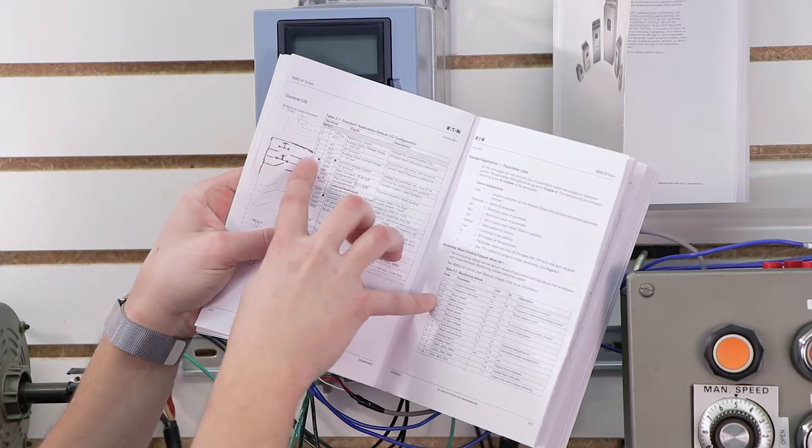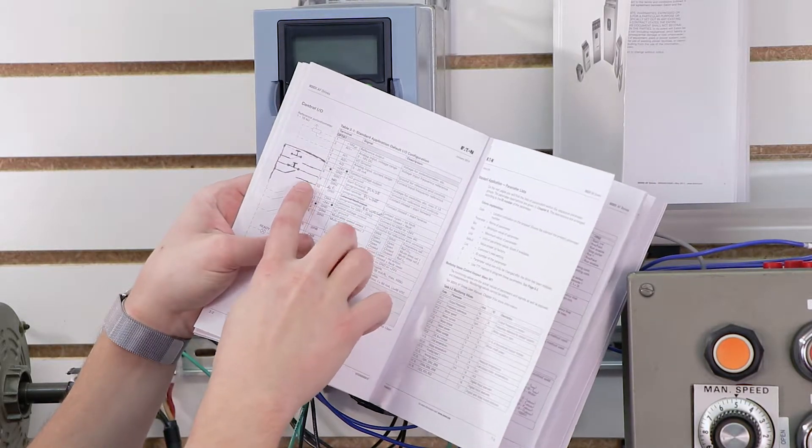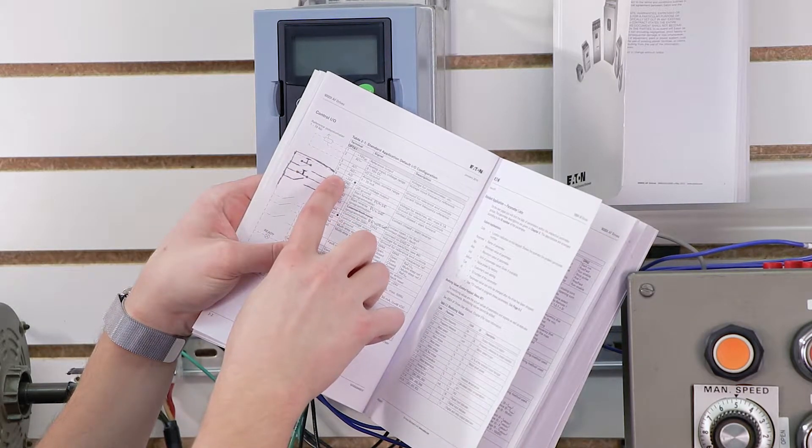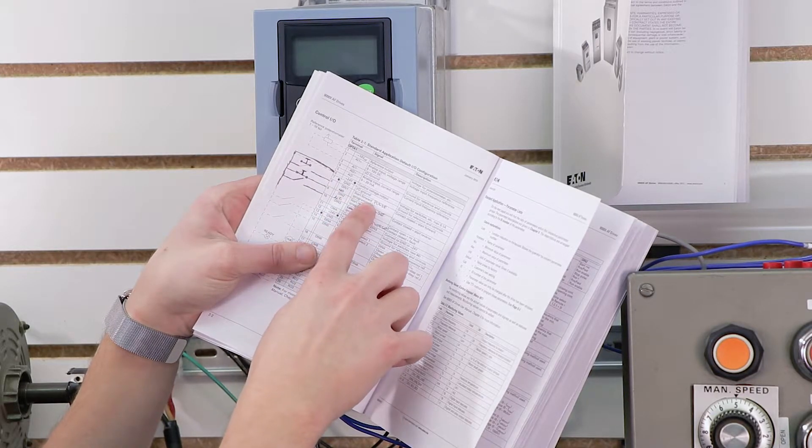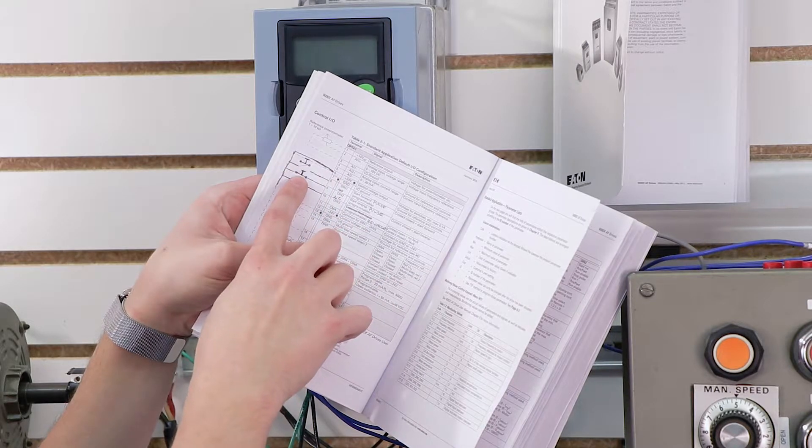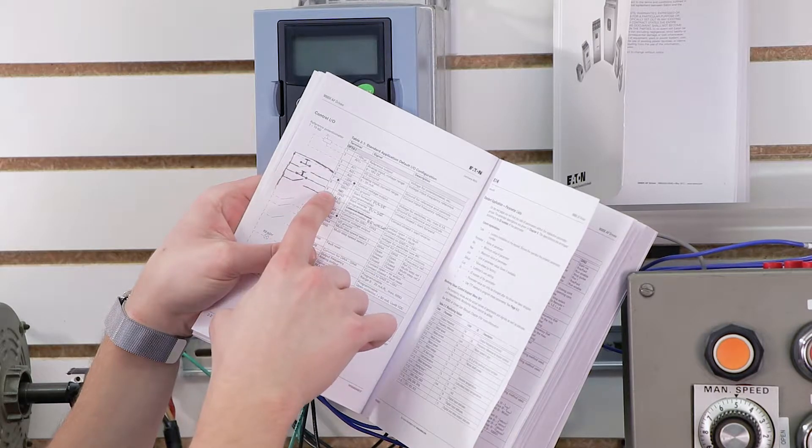So what I did in the manual was I modified the standard application macro, which we will actually set up here after we've done our wiring, and I've modified it so that I have a normally open push button that goes between terminal 6 and terminal 8, and that's for my start forward, which will be programmed for pulse, and then I wired a normally closed push button, which is my stop button, going from terminal 6 to 9, which will be stop pulse.